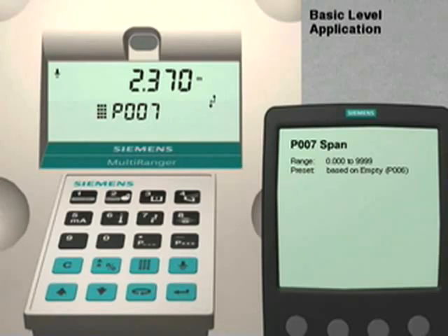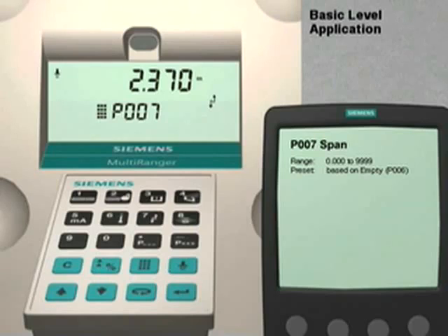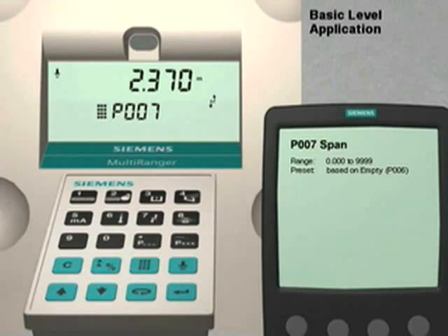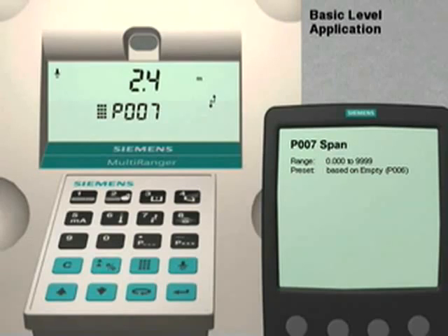Press the up arrow key to go to the final quick start parameter. Parameter 7 is the span setting. The span is the distance from the bottom of the vessel to the highest liquid level under normal operating conditions. For optimal performance, the maximum level value must be at least 0.3 meters from the transducer face. This is also referred to as the blanking distance. The maximum span value would then be the empty distance minus the blanking distance. For our application, the maximum span value would be 2.7 meters minus the 0.3 meter blanking distance, or 2.4 meters. We enter 2, decimal 4, and then press the Enter key to set this parameter.